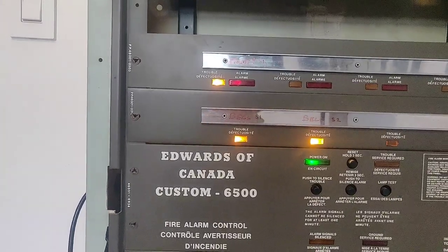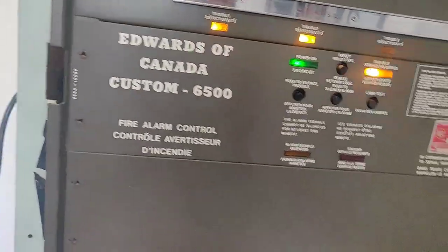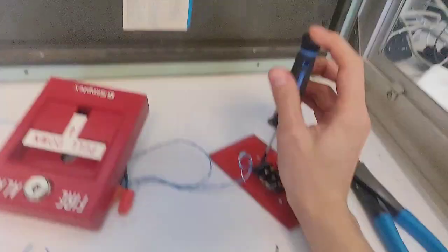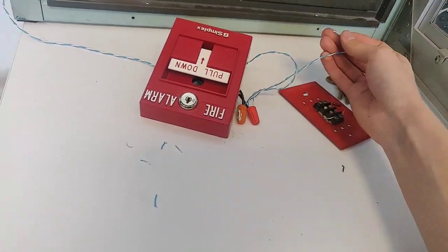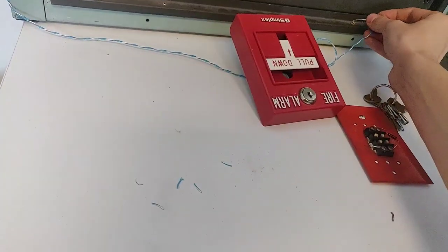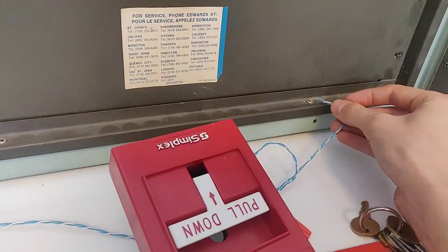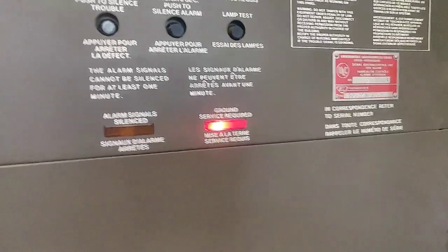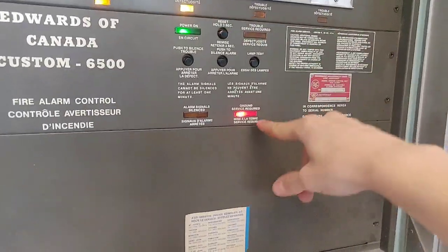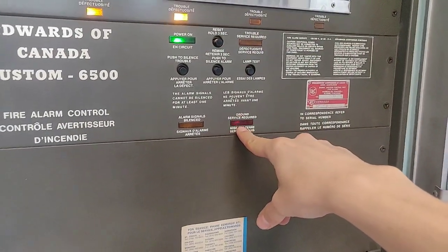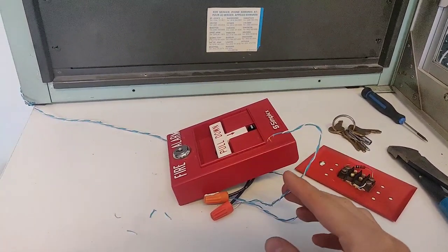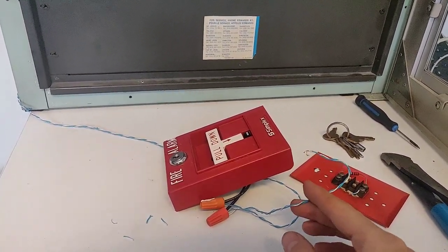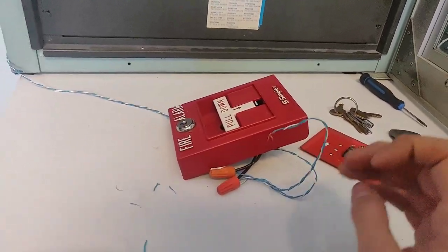Now I'm going to test the ground fault circuitry in this panel. So let's say we're having a real bad day and the wire gets skinned. That wire is still hooked up. Watch this. I'm touching it to that screw. Ground service required. So the panel is seeing that there's a short to ground. So now let me remove this and I believe if I hit reset the ground fault should go away. See ground service? Oh no, it just fades out. It takes a minute. I guess if it's intermittent it does that.